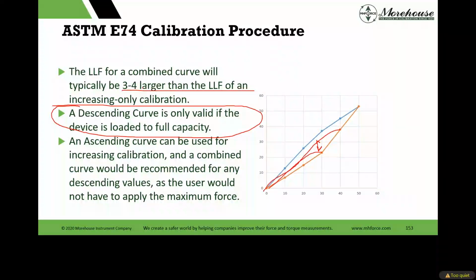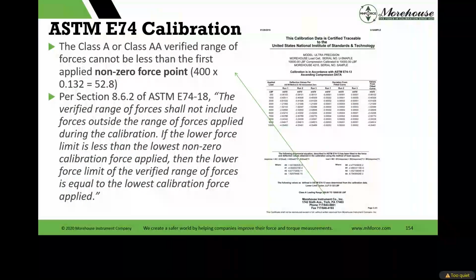An ascending curve, generally the way load cells work, they don't care as much if you only go to half capacity, as long as you've exercised it recently, and then there's material properties and all that. But on the descending curve, they always want you to go capacity to capacity, because if you only go to half capacity, you'll get a different curve coming down than if you go to full capacity. So an ascending curve can be used, and then I recommend the combined, just because of how you're going to quantify the error. Just take the higher error sometimes, but you can get different load points.